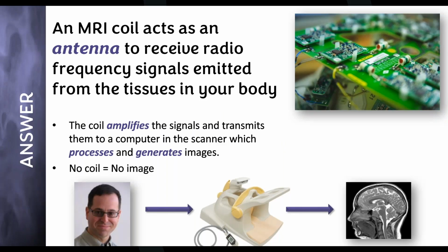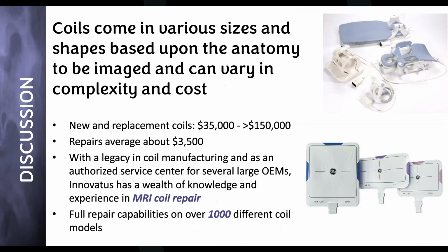Yep, for sure. And that's why there's so many coils in use on any given system. Just about any system should have roughly 15 different coils. Depends on how the MR system is being used, but they're going to be for different parts of the anatomy. So kind of expanding upon that, they do come in various sizes. There's some newer technologies out there that work a little easier. The GE blanket coils, the air coils to the right. Prices are all over the place. A newer replacement coil can be $10, $20, $30,000, well into the $100,000 range. Yeah, these new air coils are north of 100 grand.